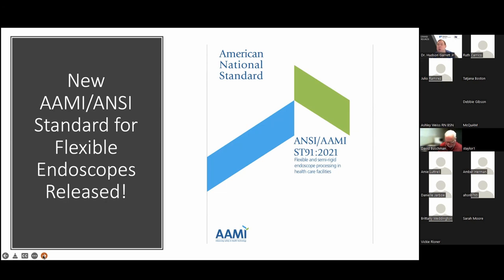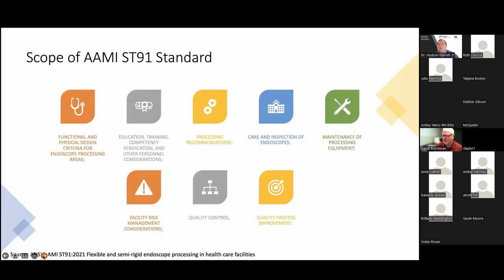This one had been long awaited, and it really looks at best practices for reprocessing. What you'll find in here, though, is that it's a little bit contradictory in terms of what the FDA has said. The FDA has really advised to go down a path of single use if at all possible, whereas AAMI talks more about moving towards sterilization. So you'll see some discrepancies associated with that.